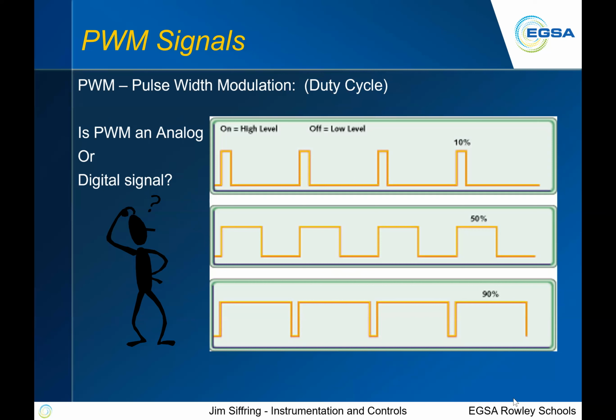That signal is a constant frequency, but the amount of on time changes, and that can be anywhere from 0 to 100%. In these three examples, the top one is a 10% on signal, the middle one is 50% on, and the 90% on is the bottom one. So what does that mean? It means that on and off signal can be proportional to some value of something else, whatever it is that we're looking at. And we use PWM for all kinds of different parameters. So is PWM an analog or a digital signal? Well, PWM is actually a method of digitally encoding an analog signal.